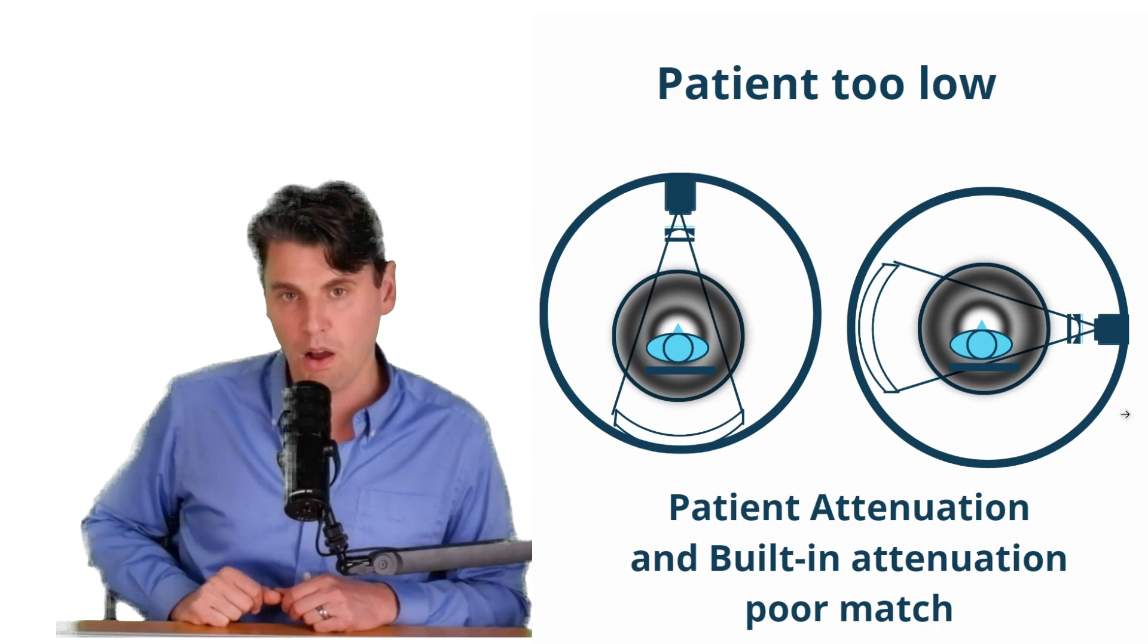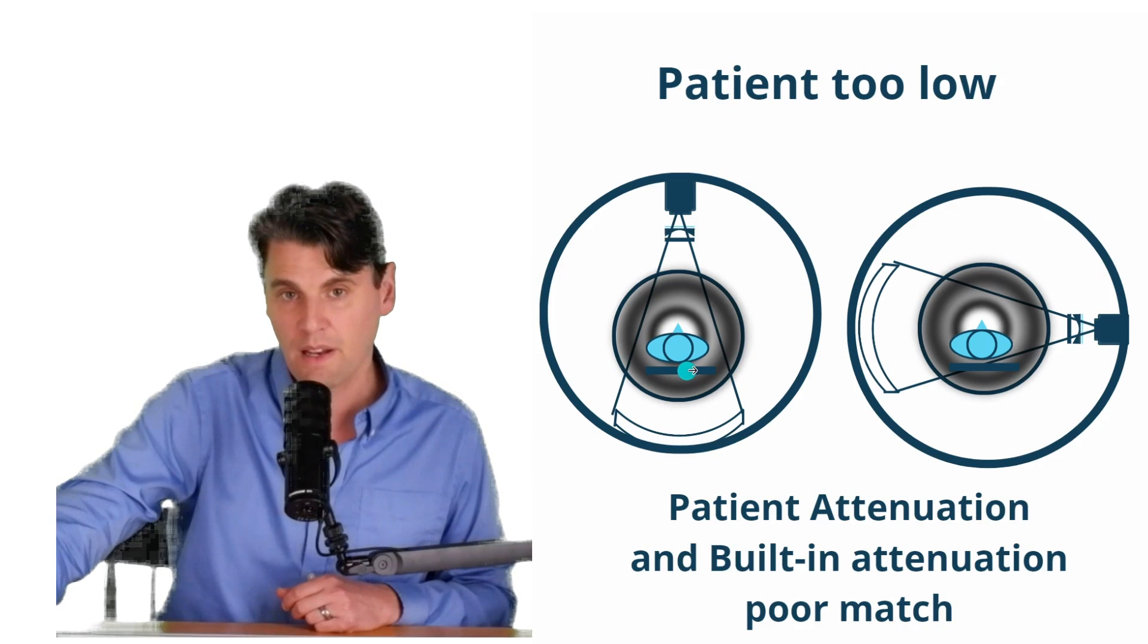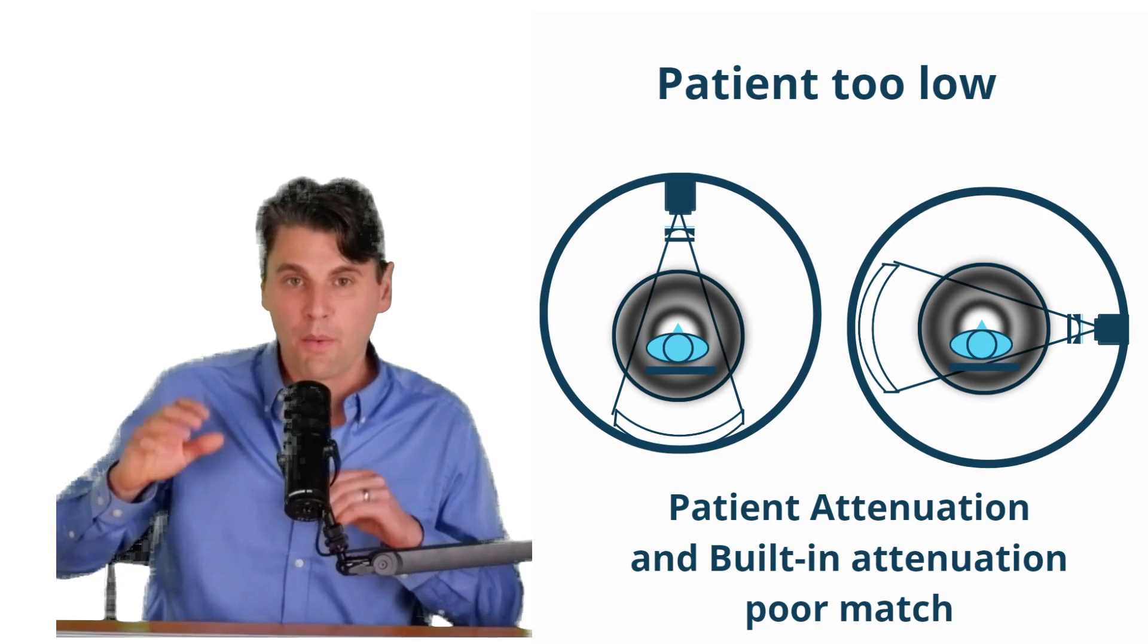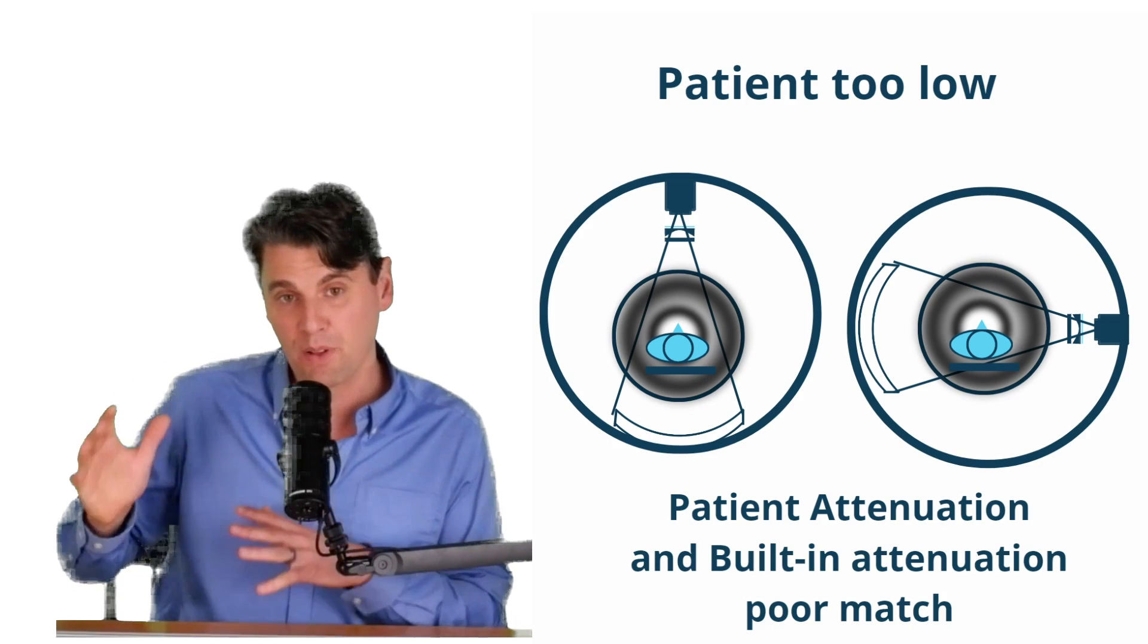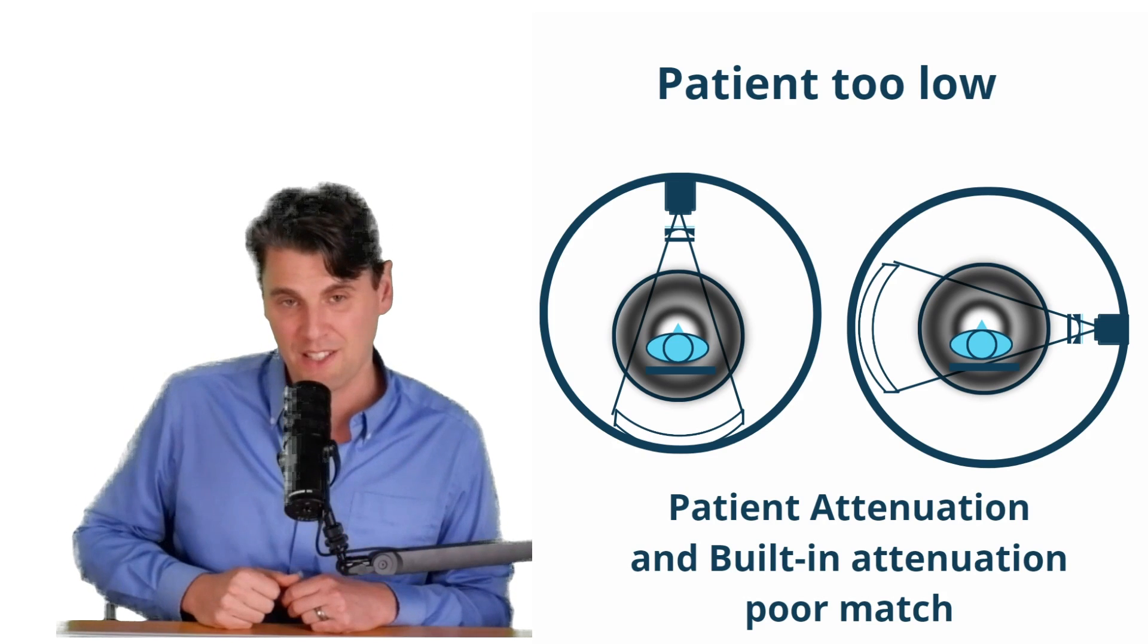Again, if your patient's too low, what you'll see is actually the opposite effect. So again, if the patient's lying on their back, you would expect to see more noise around their spine because there's a mismatch between the built-in attenuation of the bowtie filter and the actual patient attenuation.